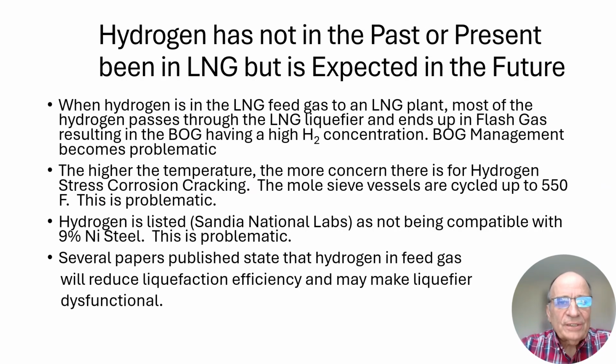Hydrogen with an H has not in the past been a component of LNG, nor is it presently a component of LNG. However, there's been a lot of discussion about injecting hydrogen into the natural gas pipelines, and if that happens, it will become part of the feed gas to LNG liquefaction systems. When hydrogen is in the LNG feed gas, most of the hydrogen passes right through the liquefier and ends up in the flash gas. That makes BOG management difficult.